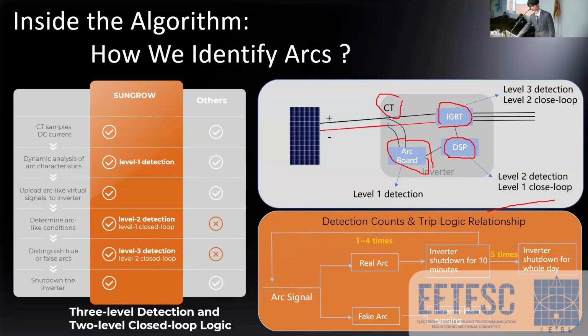And the right corner here is the trip logic. We set a trip logic for the inverter. If one day there are fewer than 5 real arcs, the inverter will shut down for 10 minutes and then automatically restart. And if a real arc is detected more than 5 times, the inverter will shut down for the whole day and must be fixed by a human and then manually restarted. So that's the trip logic.